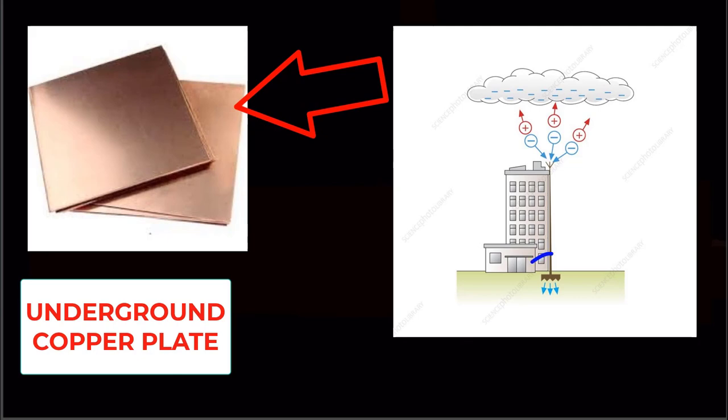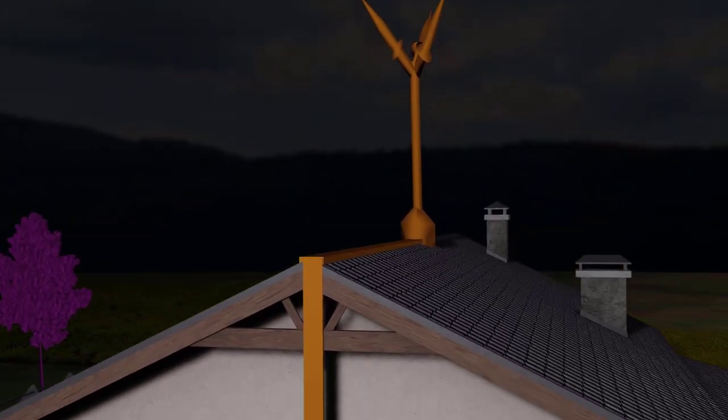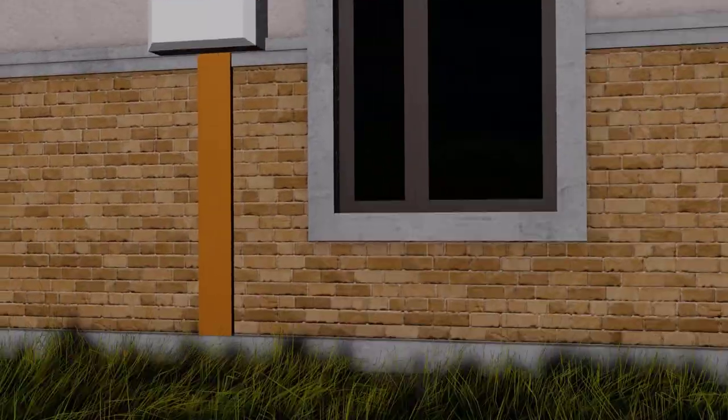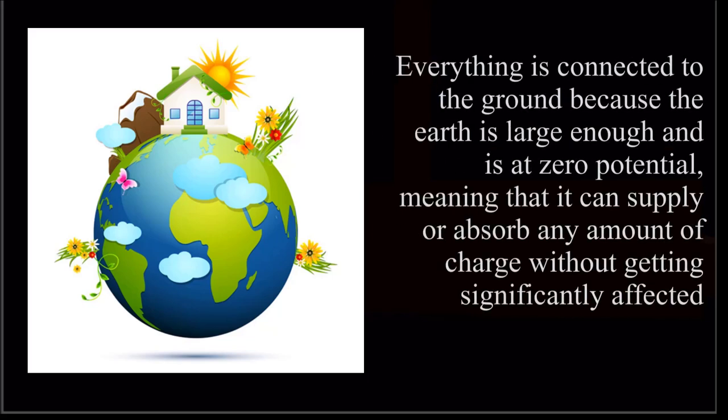The copper plate increases the surface area of contact between the earth and the lightning conductor. Meanwhile, the copper strip is thick enough to conduct current to and from the earth with less resistance. Everything is connected to the ground because the earth is large enough and is at zero potential, meaning that it can supply or absorb any amount of charge without significantly getting affected.